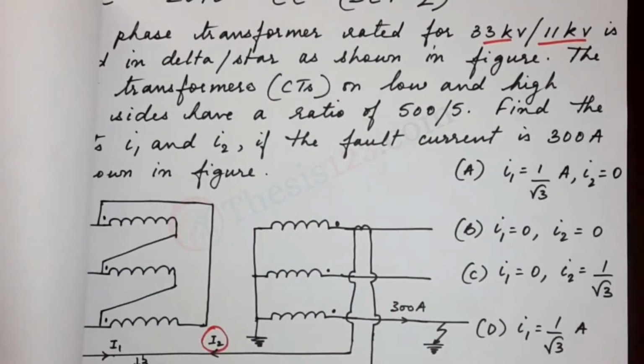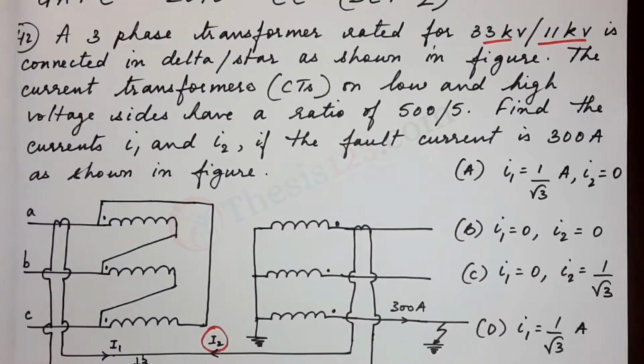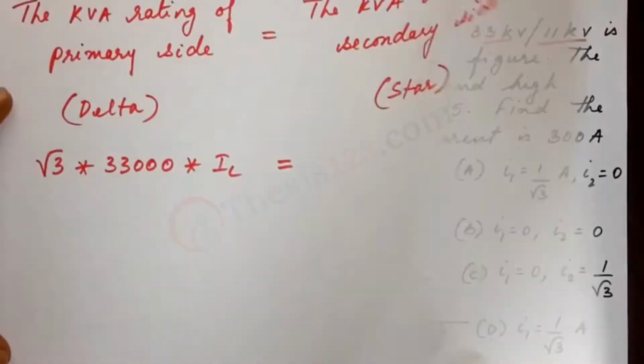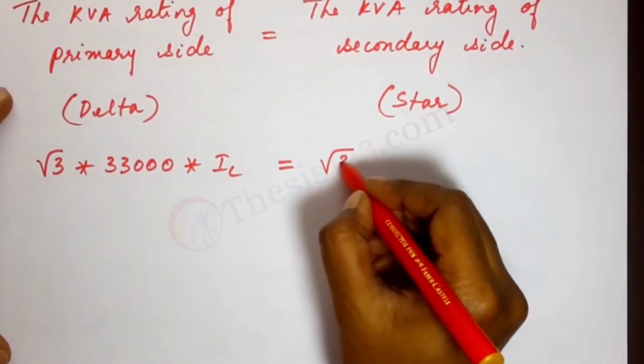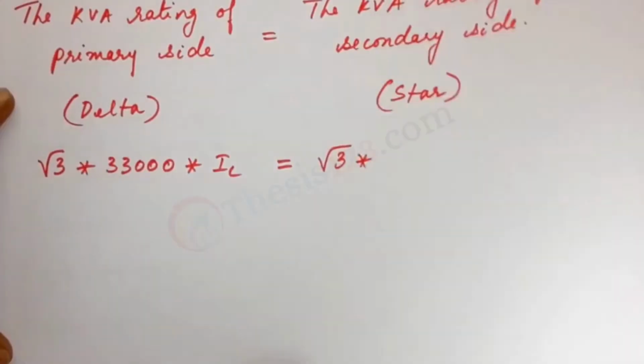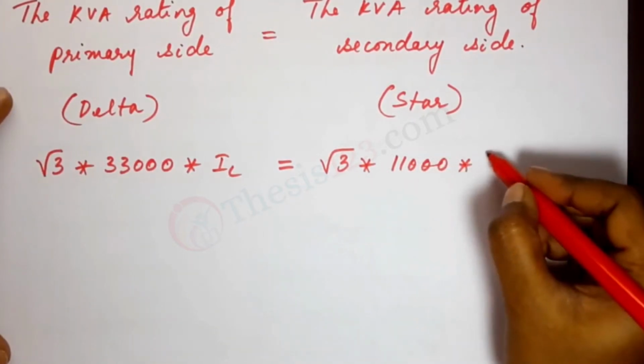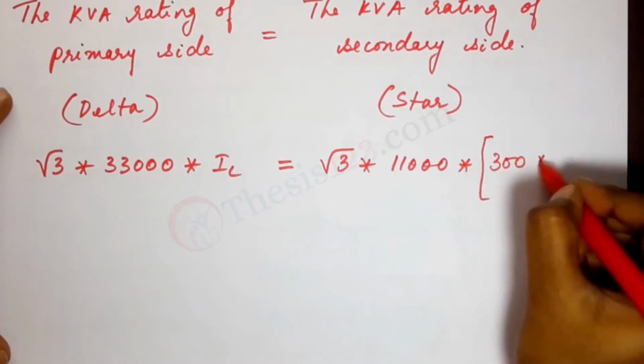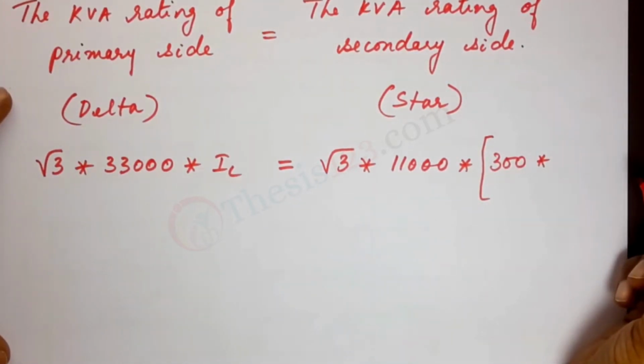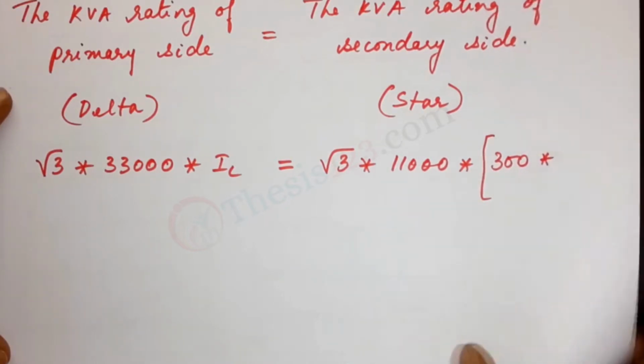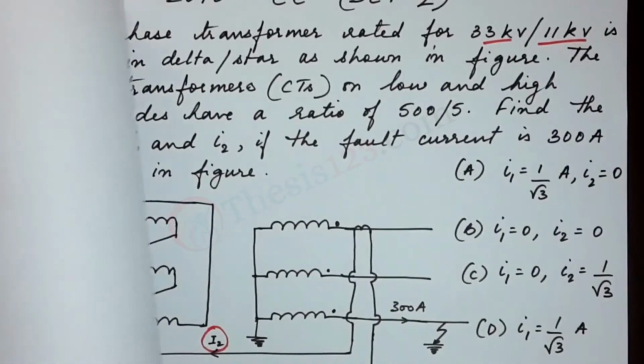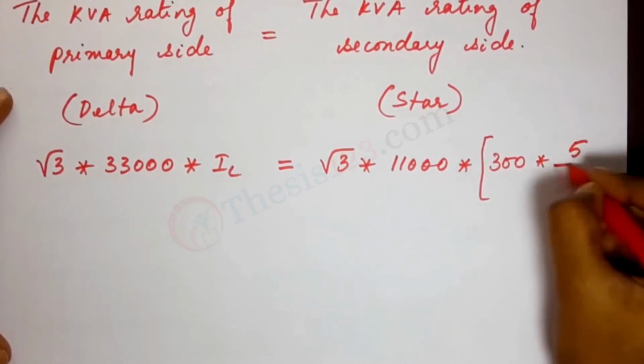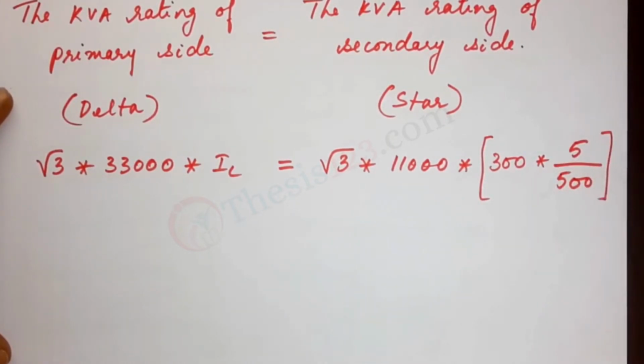take a look at the star side here. We have the current as 300 amps, that's the fault current. And we also have the current transformer ratio given to us as 500 by 5. And note that it has been written, its low and high voltage sides are given as 500 by 5. So we have to keep that in mind too. This side we would have root 3 into, the voltage is 11 kV, so that's 11,000 into, now it's time for the current. The fault current is 300 times, take the ratio of the current transformer. Now the current transformer is said to be 500 by 5 for low to high. Now we are writing for the secondary side. So be careful, you have to write the ratio in the right order. So it's 5 by 500.